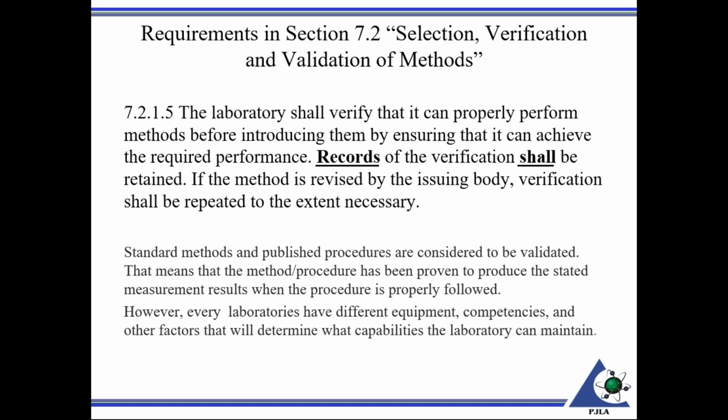The laboratory shall verify that it can properly perform methods before introducing them, and by ensuring that it can achieve the required performance. Records of the verification shall be retained. If the method is revised by the issuing body, verification shall be repeated to the extent necessary.